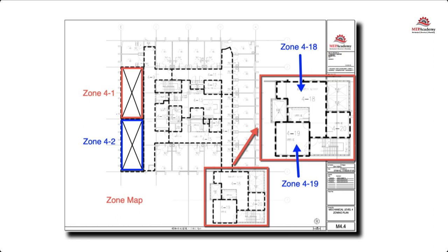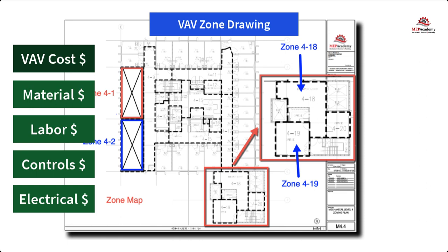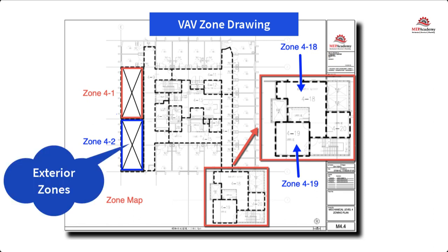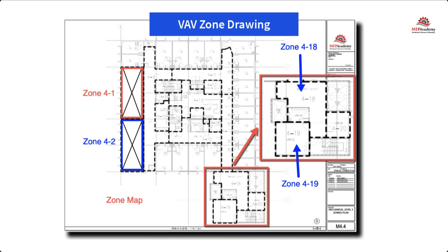One of the key elements of understanding VAV is to understand how it's zoned. Zoning is how the engineer divides up the building into separate VAV zones with each zone getting its own VAV box. To keep costs down, it's best to limit the amount of VAV boxes used, as each box adds additional costs for material, labor, controls, and electrical. After a heating and cooling load is completed on a building, the spaces can be divided into zones. Each individual zone should have a similar load profile and be served by the same VAV box. A typical zone may be offices that share a southern glass exposure or interior spaces. The idea of zoning is to break down large areas of a building into smaller zones with similar load profiles.